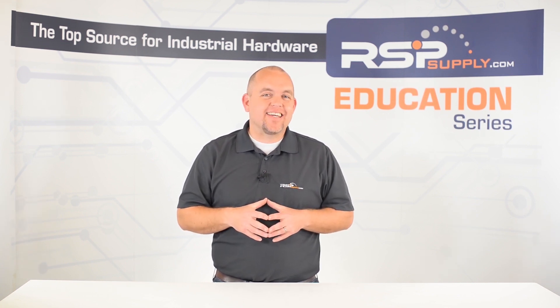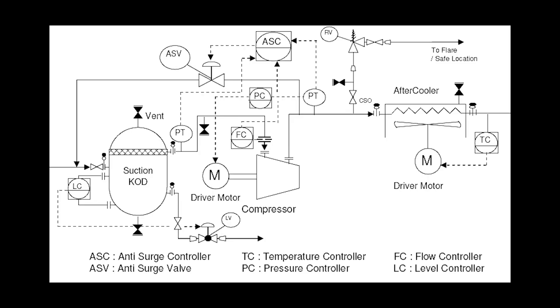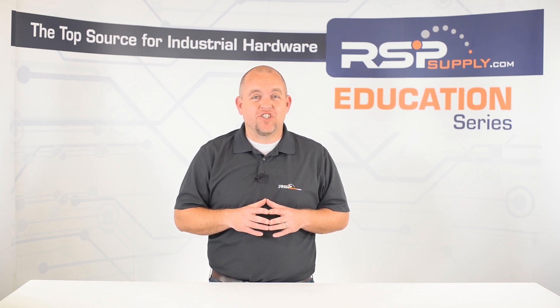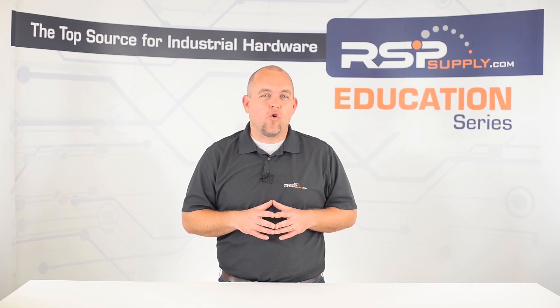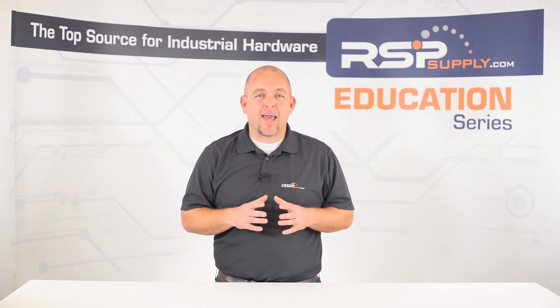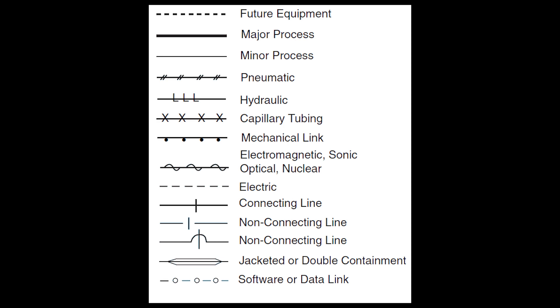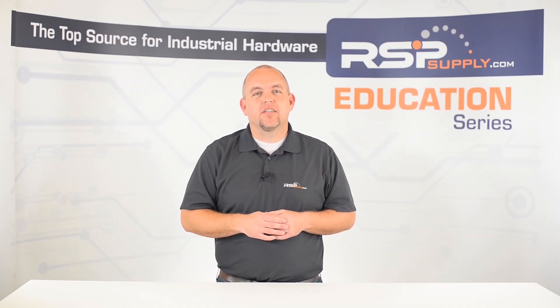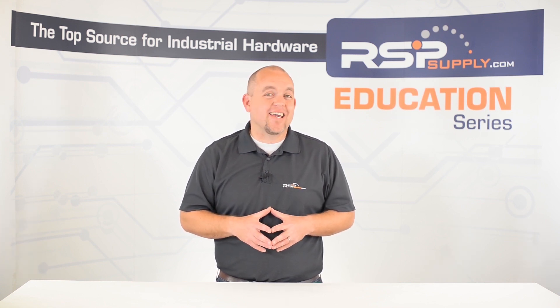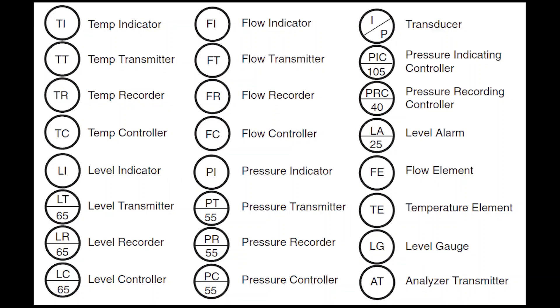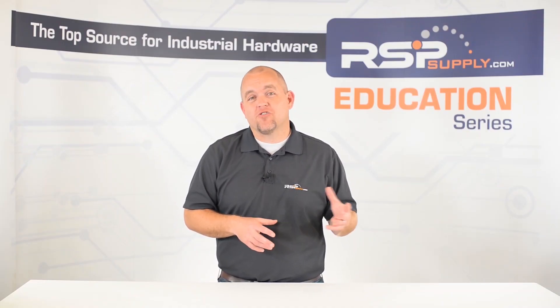P&ID stands for Piping and Instrumentation Diagram. Its intended purpose is to provide information about the piping and material in those pipes. It also references devices and instrumentation that interface with the piping and is intended to control, monitor, move, or store whatever is in the pipe, whether it is a gas or liquid. Within the diagram, it will provide detailed information about the actual pipe that is required, what types of instrumentation need to be used, and more importantly, where in the process they need to be located. Some examples of devices and instruments commonly found in a P&ID drawing include things like valves, pumps, flow measuring devices, pressure sensors, collection devices like tanks, and many other types of process equipment.